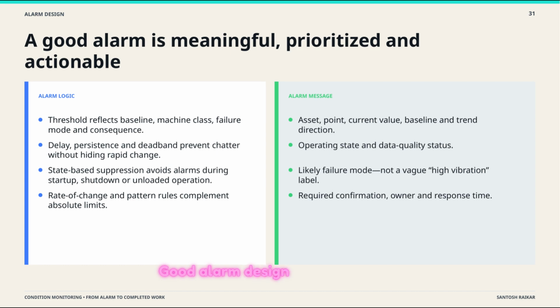Good alarm design avoids chatter. We use delays and state-based suppression, so we don't get alarms during a normal startup or shutdown. The alarm message itself should be informative, telling the owner what the value is, what the baseline was, and what the likely failure mode might be, rather than just a generic high alert.